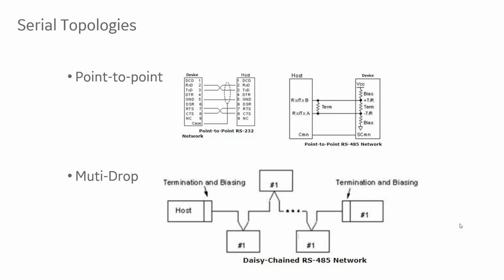So in terms of topology for serial, there's the point-to-point. So this is like when you connect your laptop directly into your relay, the front panel. Then you have your multi-drop, like your RS-485. So you have multiple devices daisy chained together. The disadvantage of using this multi-drop is only one device can occupy the communication with the host at one time. So you can't communicate to multiple devices at the same time. So you have to do some sort of polling. So you have to do some sequential polling to be able to get that data.